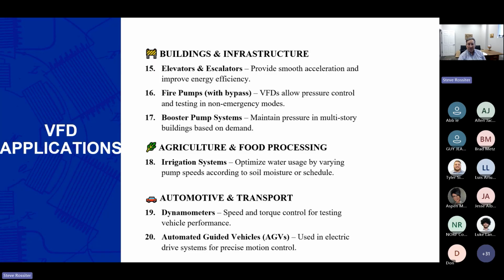Elevators are a no-brainer. Almost all of those were DC before. Now they're almost all AC drives. Booster pump stations in a multi-story building usually stage on levels of motors, and at least one of those stages is always going to be a variable frequency drive. Now, even if there's 3 stages of pumping, they'll probably put all of them on just because of the benefits of the reliability. And agricultural irrigation systems have become very popular just because it's one of the best ways to really control the usage of water on crops.